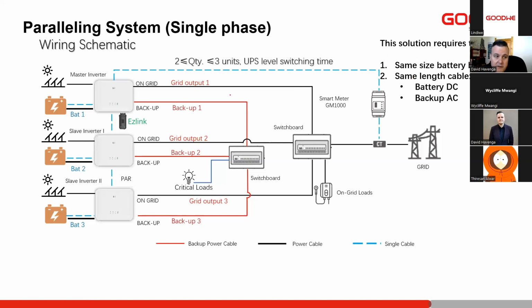In this scenario, it's always good to make sure your battery cables are the same length and your backup output cables are the same length. It's a default rule of thumb for any parallel system, not just the GoodWe parallel system, to make sure you have equal potential between the outputs to have a perfectly balanced system. You'll see the Ezlink. The Ezlink installs to the master inverter. The communication between the inverters.